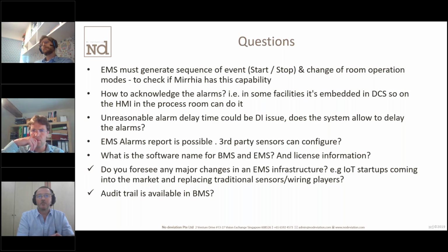So you need the control to ensure that you can see who's got the access, have the right people got the right level of access, and if somebody makes a change, you need to see that change, because there might be an issue. They make a temporary offset to a temperature just to accommodate, say, a big meeting in a boardroom, and they want the temperature to be set lower for that period of time, but then they forget to reset the value afterwards. If you've got the audit trail, you can see who changed it, when they changed it, and then you can make sure you address with them the fact that if they make those changes, they bring it back again.